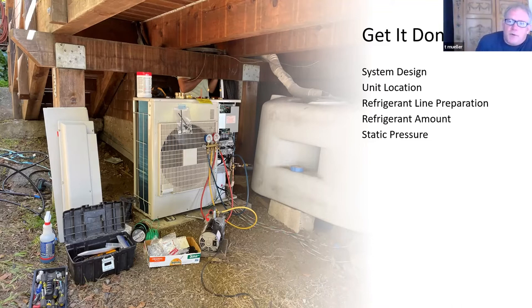Refrigerant line preparation—I'll go through these three things quickly, because it's really beyond the scope of your architecture work, but just to give you an idea that it's important these things are done well. Refrigerant lines have to be purged with dry nitrogen, evacuated, and done multiple times if necessary, based on the readings, to determine if there's any moisture left in the system.